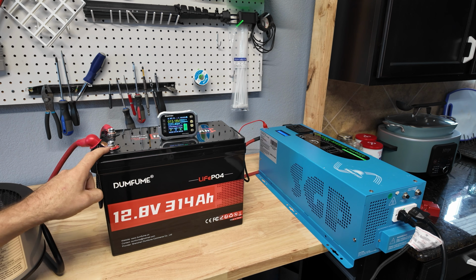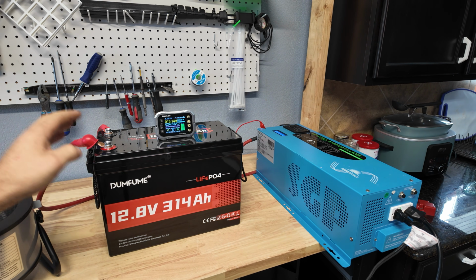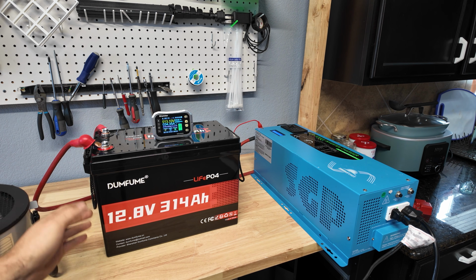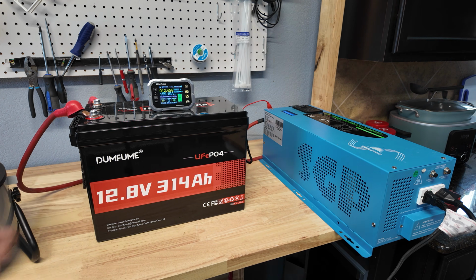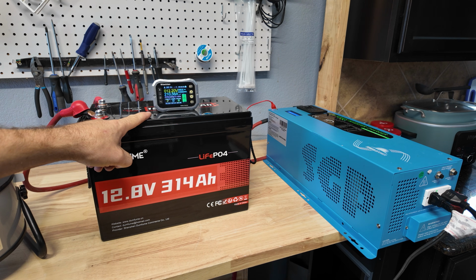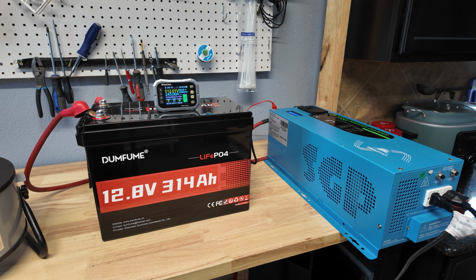Next we're gonna put a 200 amp load on the battery, and actually go higher than 200 amps just to see if the high current protection kicks in or not. So far we're at 160 amps. Now we're over 200 amps. Looks like we're settling around 245 amps - that's almost 3,000 watts of output.